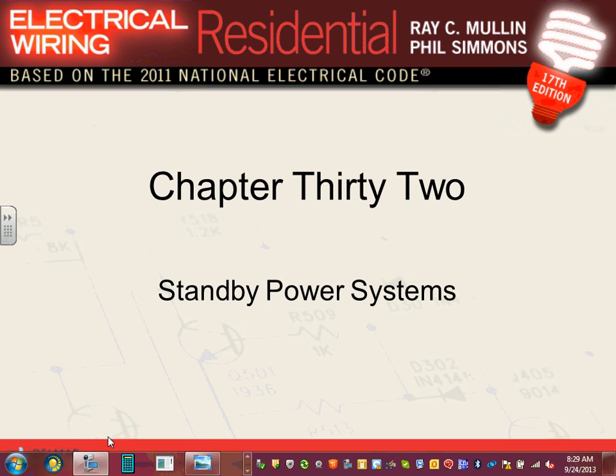The emergency system, you can solve the problem without a generator by having lights. Most of the lights, exit signs, and emergency lights need backup power. Your backup power requires either batteries inside these fixtures, or an emergency panel with an emergency generator that must synchronize and pick up the load within 10 seconds.